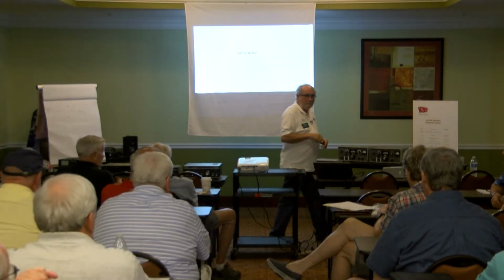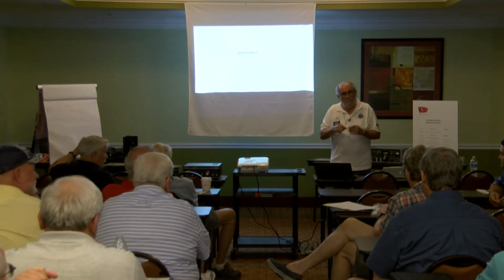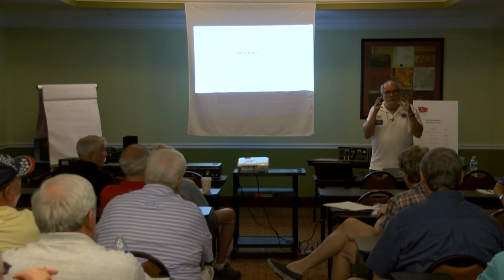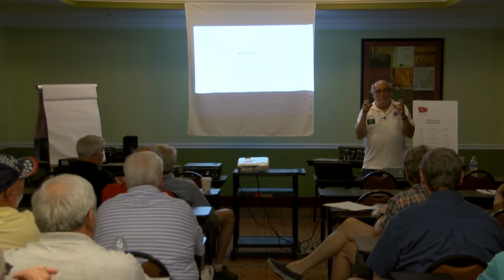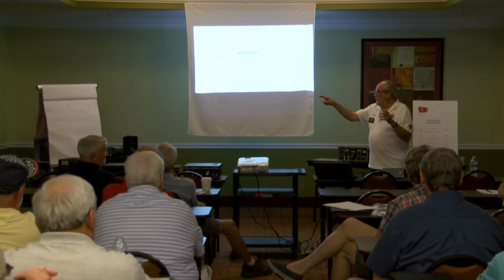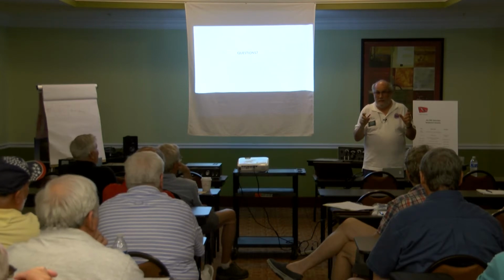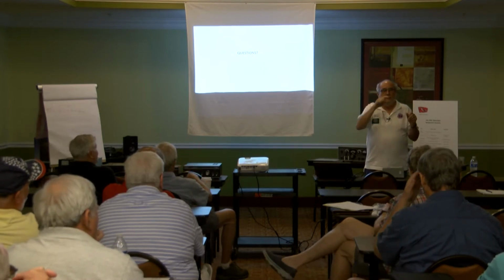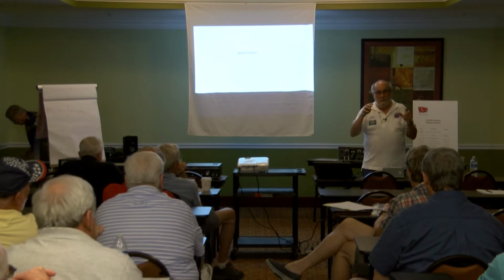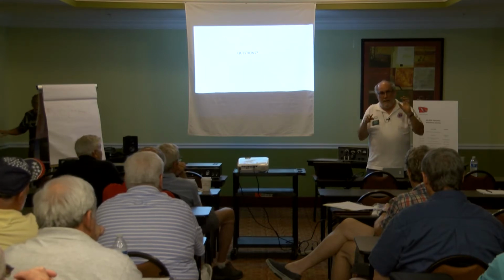So essentially what you're saying is that I have to supply the same current rating as the primary. No. We're not building a transformer. If I build a transformer to step up or step down, I have no interconnection in the windings, all right? The KVA rating of the primary and the secondary are the same. Yes, the KVA rating, not necessarily the current rating. Correct. Now I'm interconnecting the two together. If I interconnect them where the primary and secondary are in phase, then that is a boost transformer. So I'm adding the waveform of the primary to the waveform of the secondary.